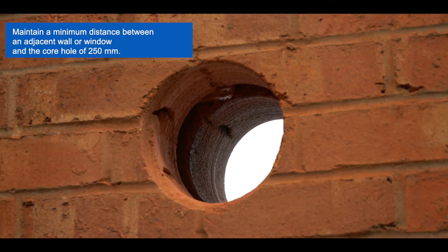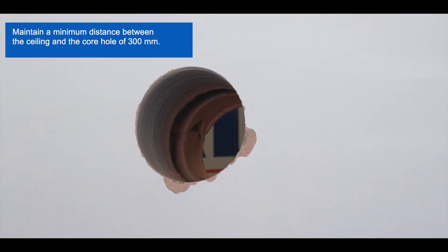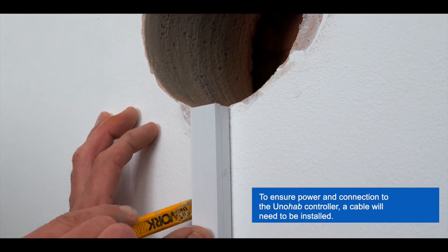Remember to maintain a minimum distance of 250 millimeters between an adjacent wall or window and the core hole. Also maintain a minimum distance of 300 millimeters between the ceiling and the core hole.